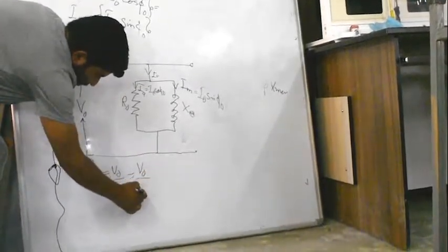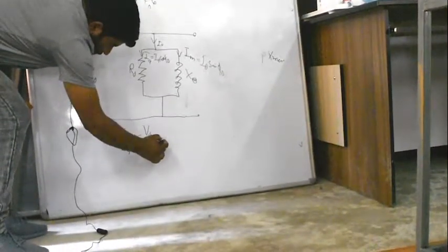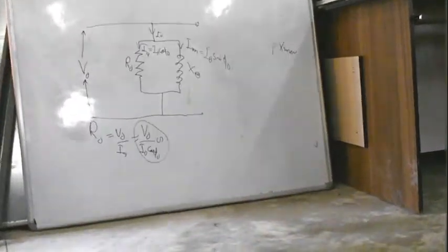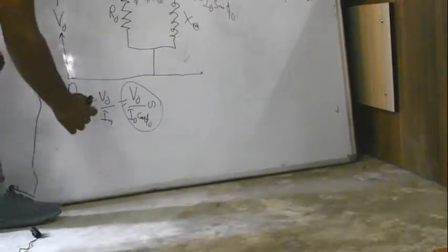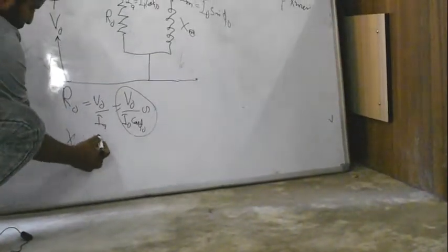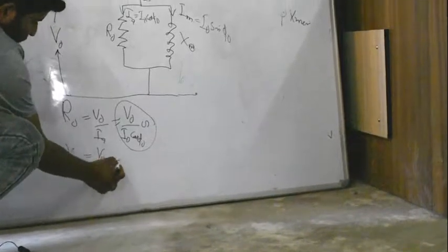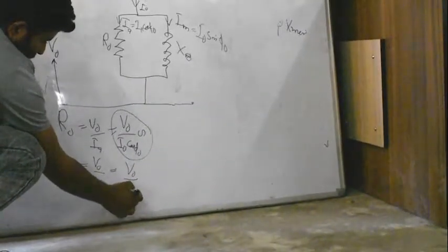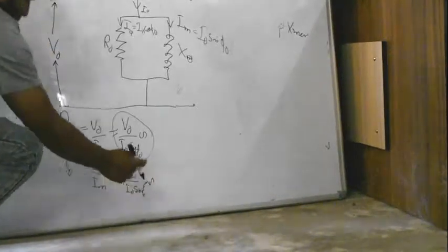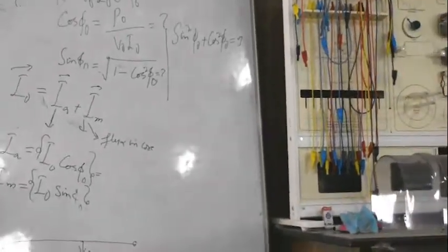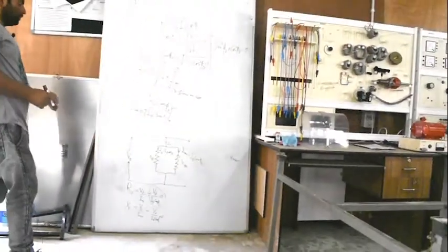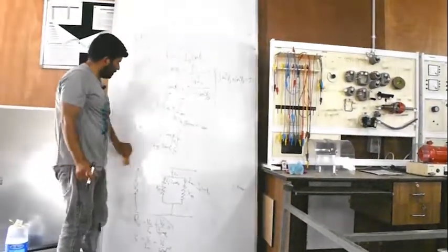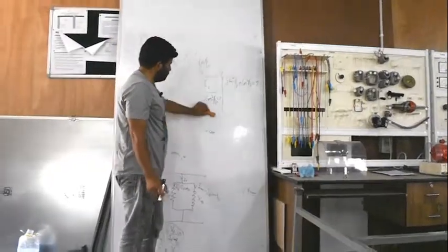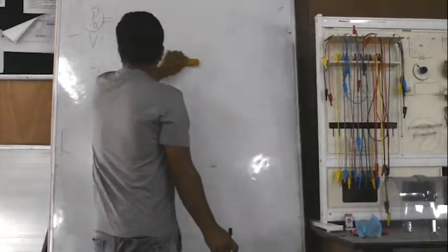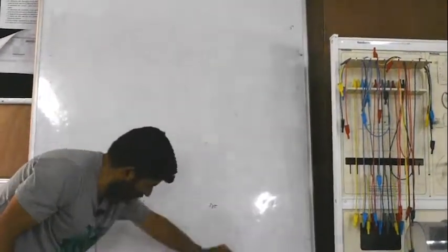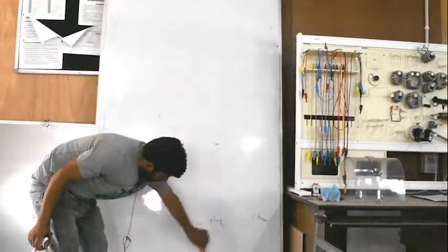This is V naught by I naught cos phi naught. This much of ohms will be R naught, and similarly your X naught will be the applied no load voltage by Im, which is V naught by I naught sine phi naught. So this is the data which we will be obtaining by performing the no load test on a single phase transformer. I will be repeating the whole data that you have obtained from a single phase transformer by performing the no load test.